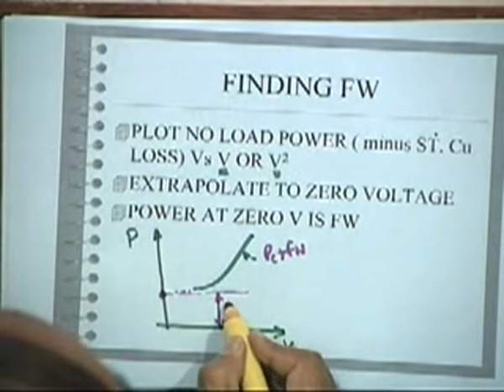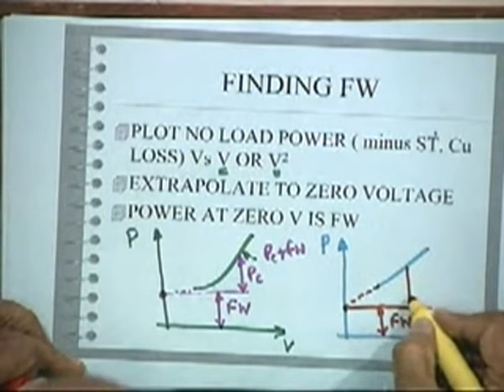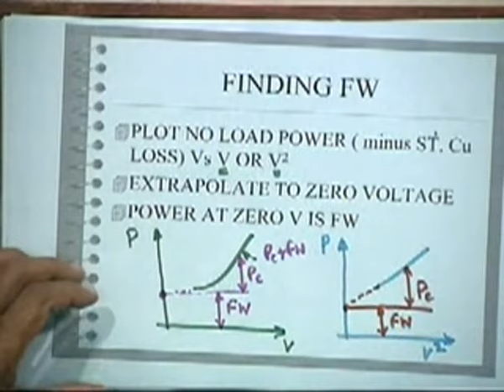at the corresponding voltage, okay. Of course, the more convenient way also is if you plot P by V square, and if it is like this it will be linear. P by V square will be linear because the Pc is proportional to V square. So here it is easy to extrapolate. So this will be the friction windage, and this will be the Pc. This is versus V square, because Pc versus V square is linear. Pc is proportional to V square, or K times V square. So this is one of the prescribed test methods to find out friction windage, okay.